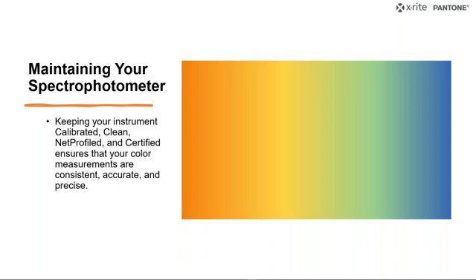And that ensures that your color measurements are consistent, accurate, and precise, right? And hopefully it allows you to focus then on the root cause of any real color variation. So if you know you're maintaining your instrument properly, you're doing all of these things, you can have great confidence and faith in your device. Your device is doing it right. So if your device is reporting a color difference, it's real. It's not something that might be contributed to by the instrument having drifted, so to speak. So it allows you to focus on the real color variation problems that may exist.